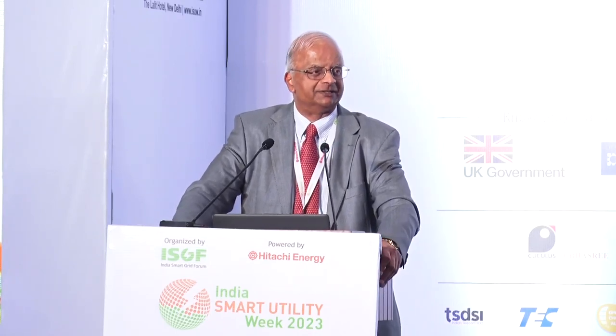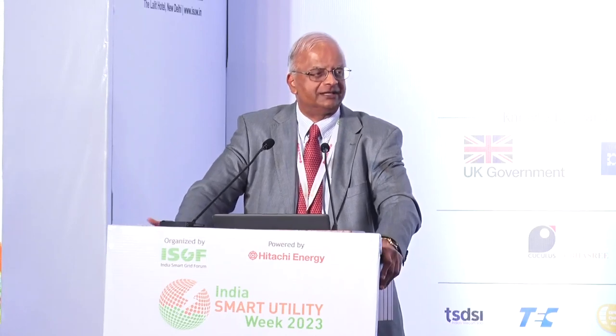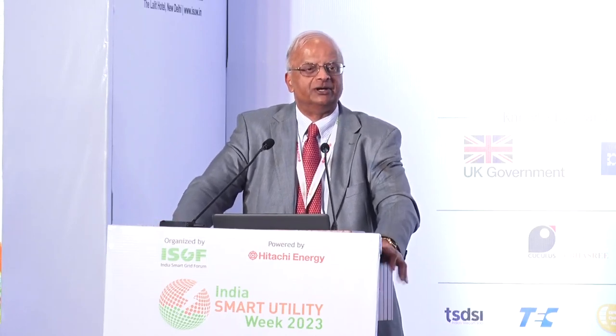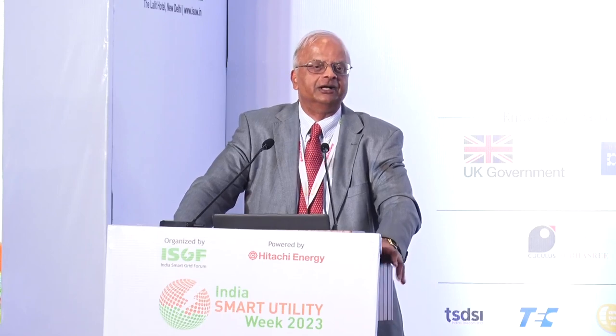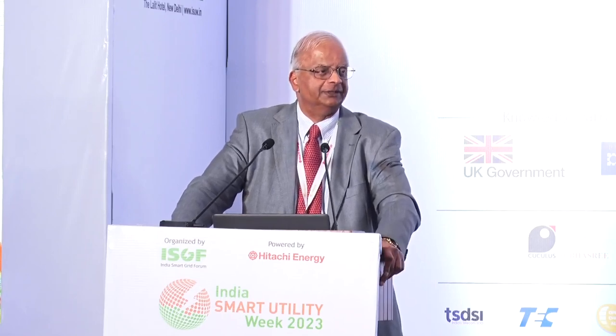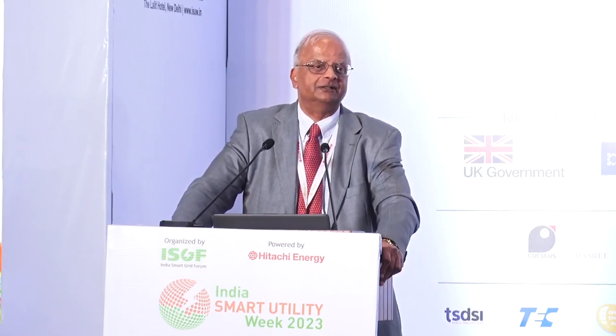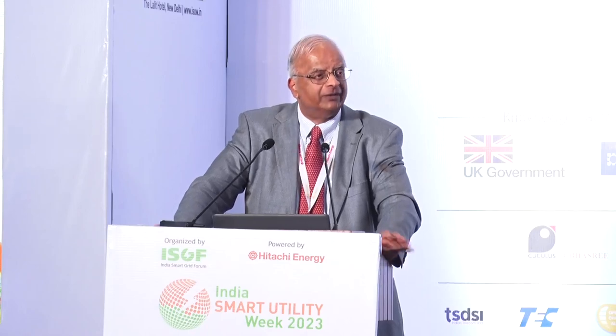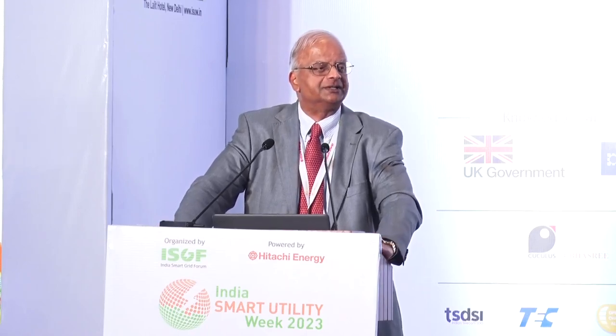The second case is on cables. I mentioned the 90-degree cable — if you take the conductor temperature to about 102 or 103, you've lost 30% of the cable life. That's how punitive it is. We've put this across electrical utilities in America.